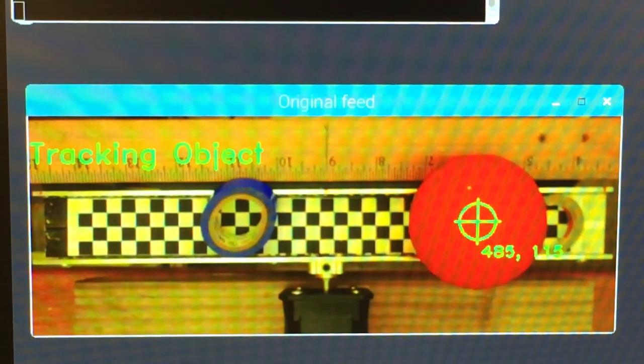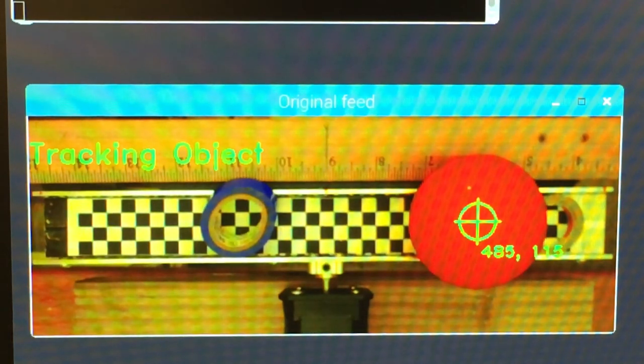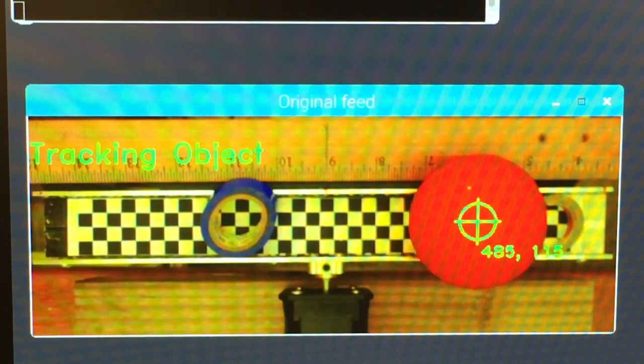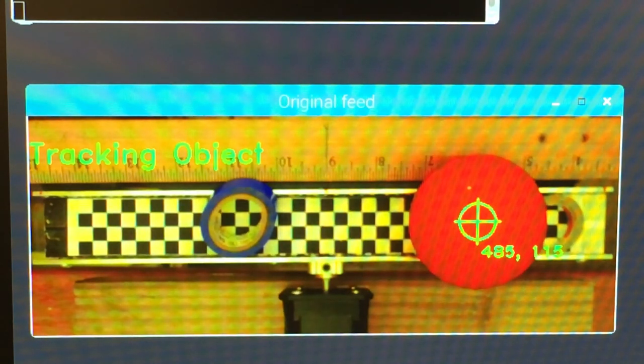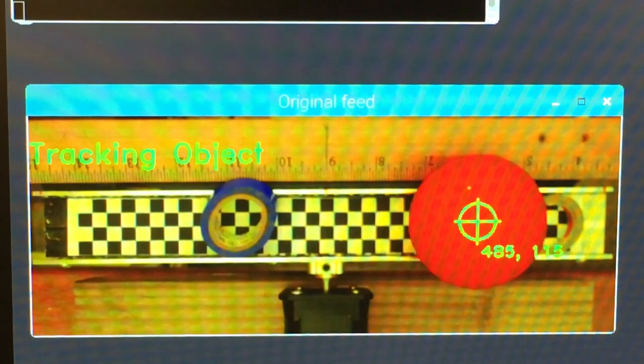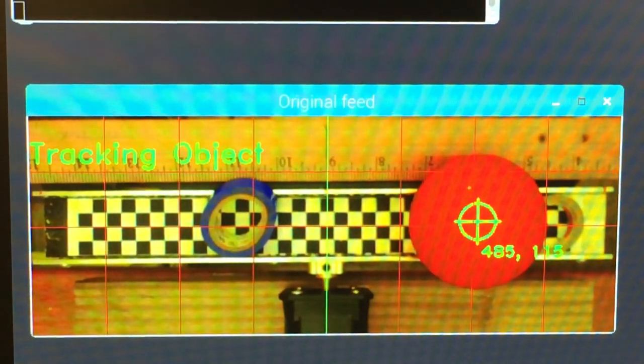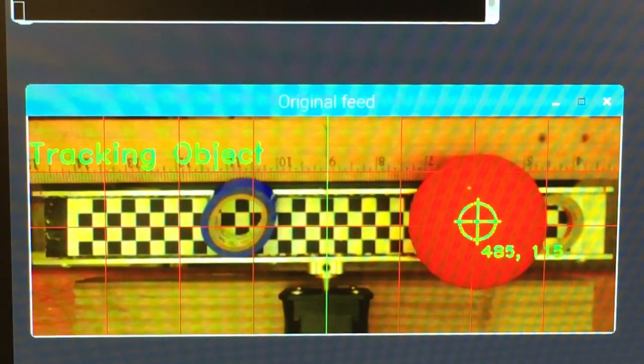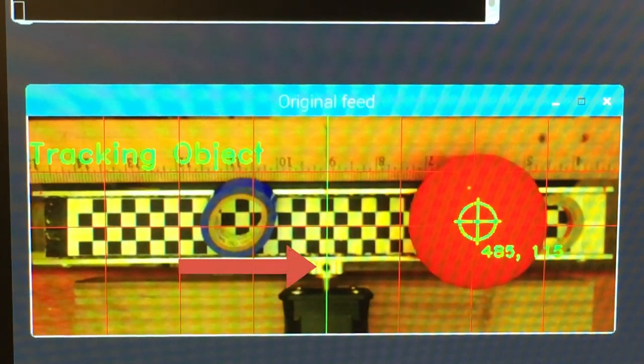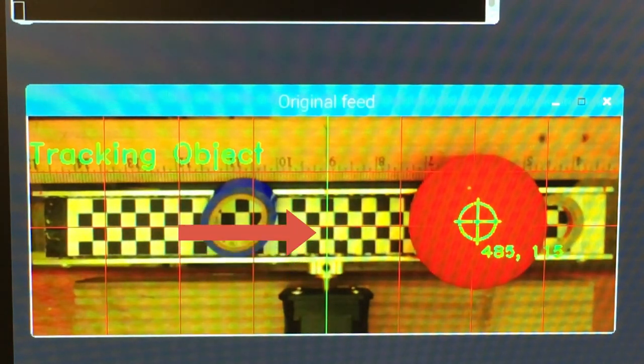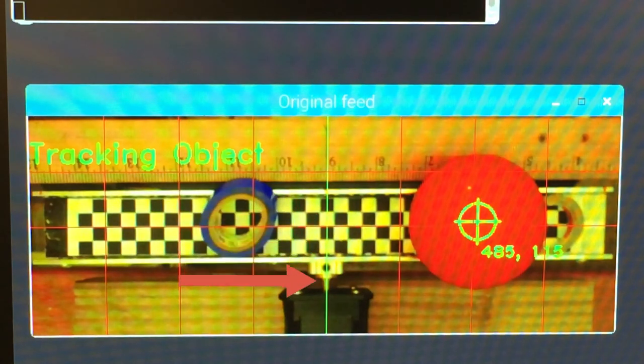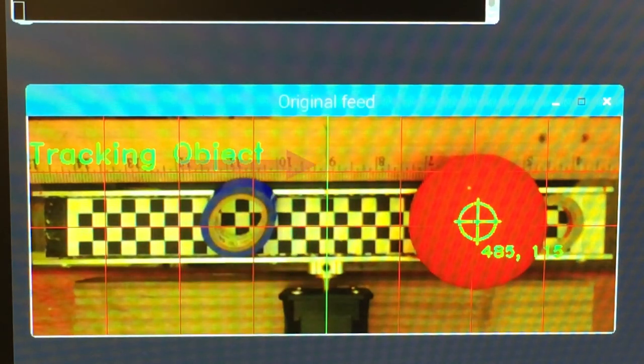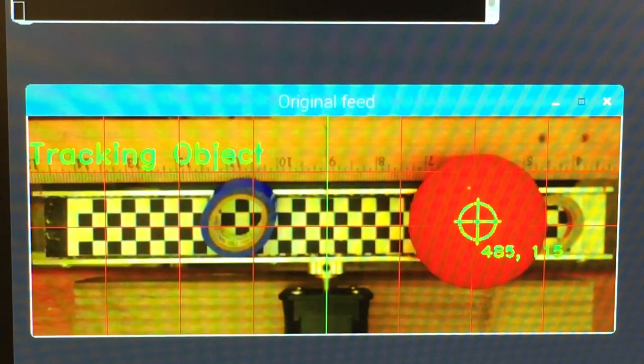In the video, which unfortunately is not the best quality, I'm still learning video on the iPad. You see a close up of the beam, the checkerboard pattern and the ruler. When I superimpose the grid on the image, you see that the center of the beam lines up pretty well with the center vertical grid line. It also passes through the 9 inch mark on the ruler. So they're good signs of alignment.